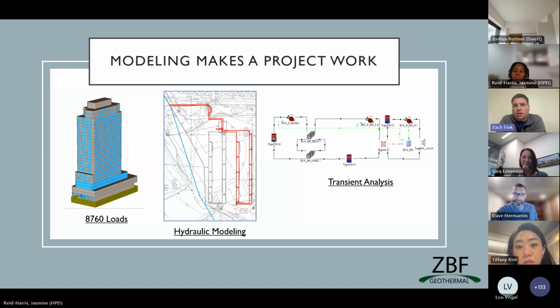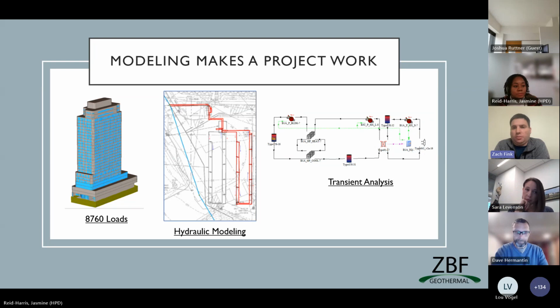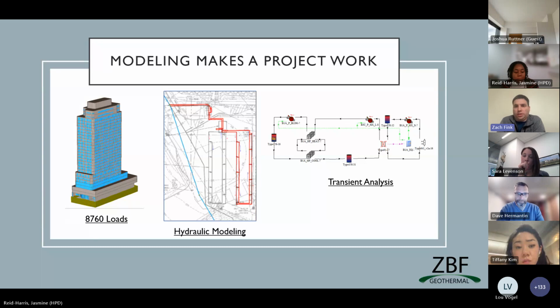So we talk about modeling. The baseline to make sure you have a robust geothermal system is an 8760 energy model, which predicts how the building operates every hour of the year. We look at coincidentals between when domestic hot water is generated and when heating and cooling is used, and how the sun hits the north and south sides of the building. It looks at how the building peaks - not necessarily your connected load, but your diversified peak load - which lets us size the bore field.